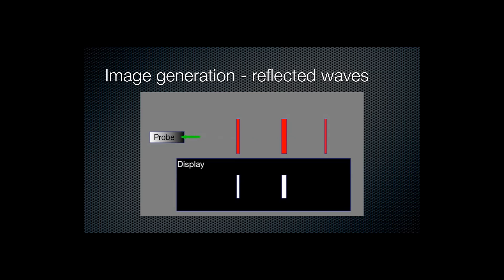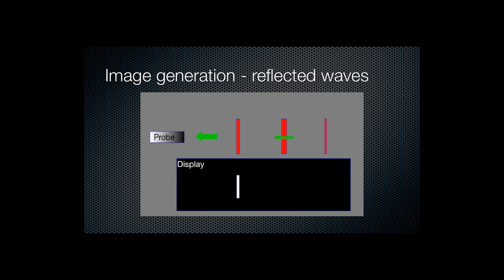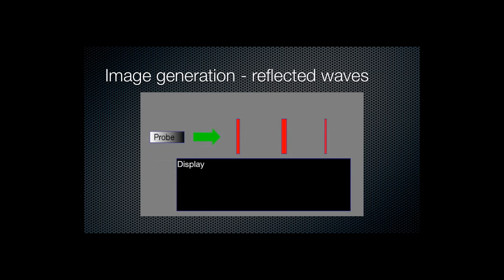So in order, the brightest signal or densest signal will come from the thickest reflector, the one in the middle, less from the first reflector, and much less from the deepest or furthest reflector. You can also see the influence of the constant velocity of propagation on the delay in display of deeper structures as the echoes are returned to the probe.